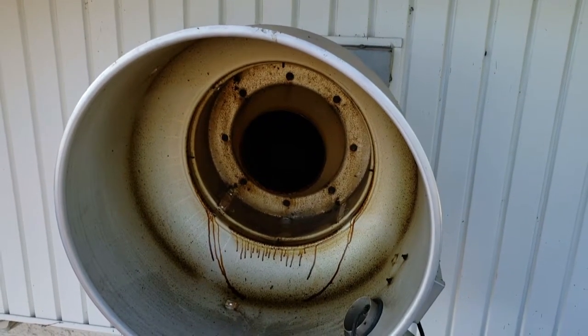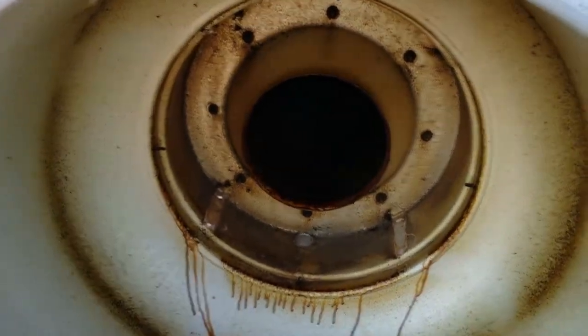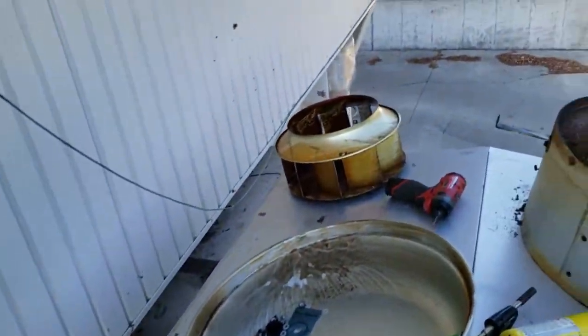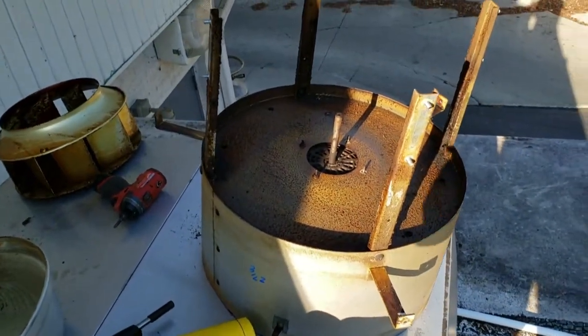These are those days where we're doing a little something different — we're doing some exhaust hood work. We had a motor that had bad start windings; it wouldn't start on its own every time.